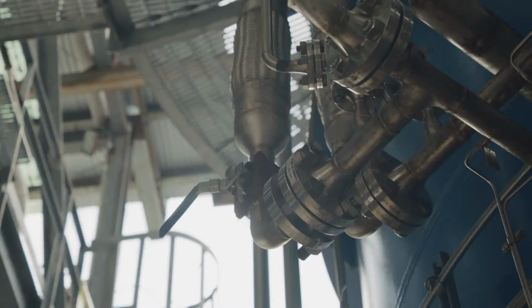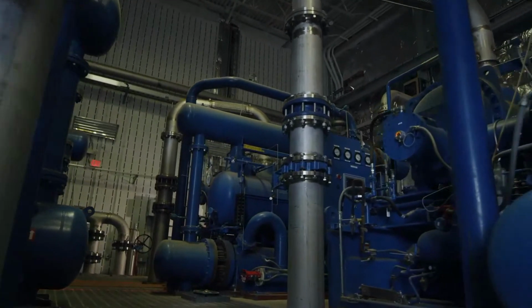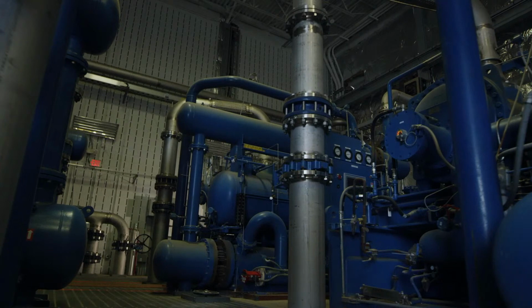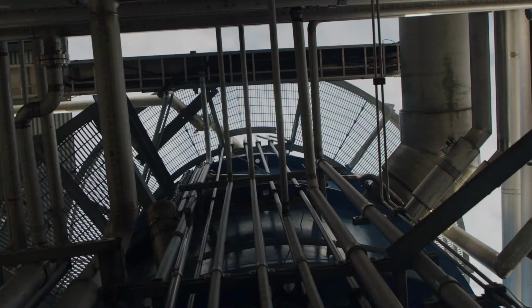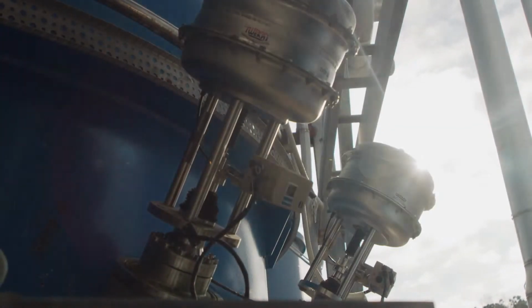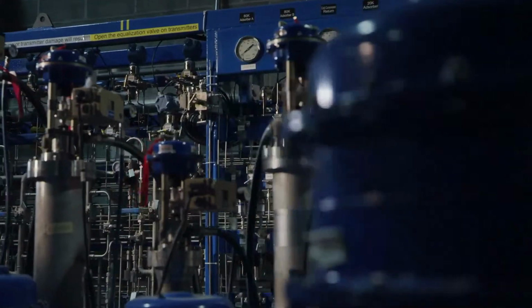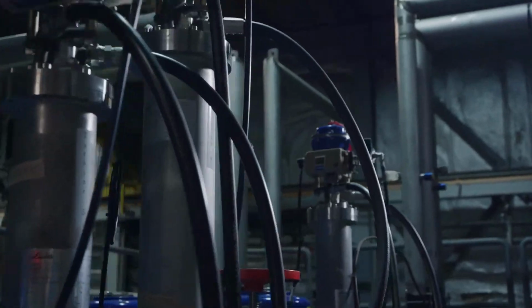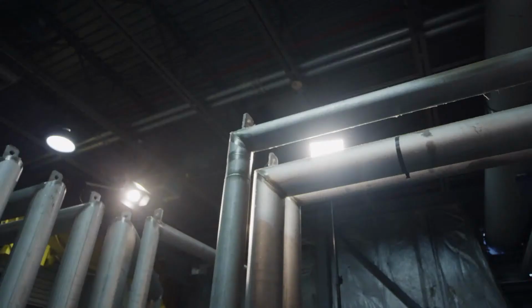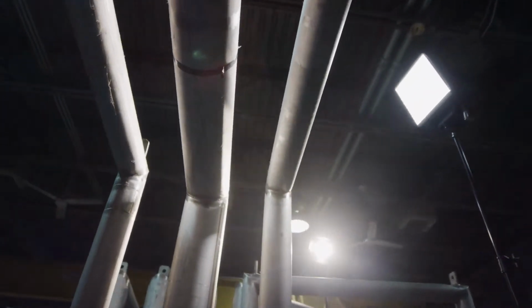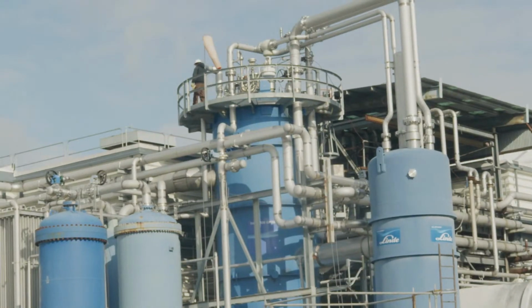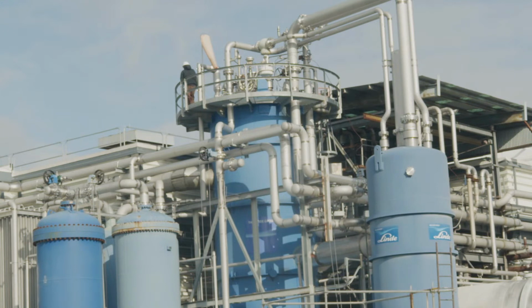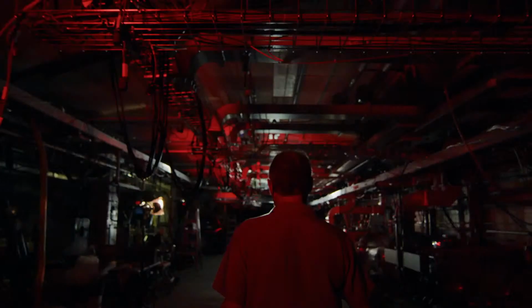The lab's two central helium liquefiers together chill more than 30,000 gallons of warm helium gas to high pressures, then send it through cold boxes. The cold boxes usher the helium through a sophisticated system of tiny turbine expanders, each spinning thousands of times per second, followed by a set of complex heat exchangers. The system removes energy from the helium and reduces its pressure until it becomes a superfluid without resistance that conducts heat freely. The central helium liquefiers work together to cool particle accelerator components and the low-energy recirculator facility to their operating temperature of 2 Kelvin, or minus 456 degrees Fahrenheit — just a few degrees above absolute zero.